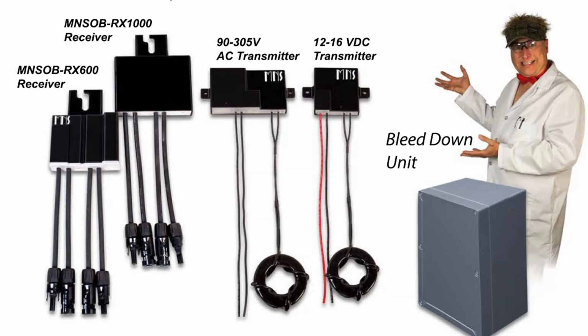We also offer a bleed down box with the MNSOB system. What this allows you to do is for any inverters that are not compliant to that rapid shutdown within 30 seconds, this will discharge the caps within the inverter so that they do meet that standard and make it safe. It includes the transmitter already, so if you are using a bleed down box, you won't need to buy a separate transmitter. You will only need to buy the receivers to go with it, and it is compatible with either the 1000-volt or the 600-volt version.